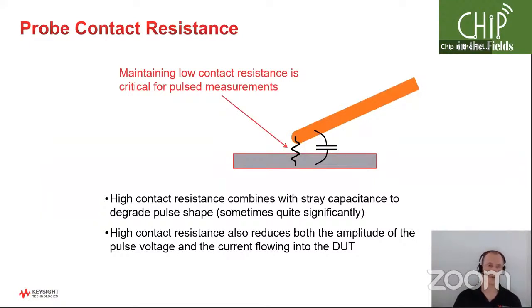Another thing that you really have to worry about, that you don't need to think about as much if you're making IV or even CV measurements, is the contact resistance of the probe. If you're probing a wafer, there's going to be a little bit of resistance from the probe to your DUT, and there's also some associated capacitance. Well, that's an RC circuit, so that can actually affect how your pulsing behaves. So you don't want to have that resistance high. If you're getting some weird results, you might want to lift the tips up, inspect them under the microscope, and maybe clean them off or change the tip if necessary, because any stuff that accumulates on that probe tip could potentially increase the resistance to your DUT. It doesn't matter so much for basic measurements, but if you're trying to make a high-speed pulse measurement, it can have a big impact on the kind of pulses that you can generate on your DUT, for the reasons shown on this slide.